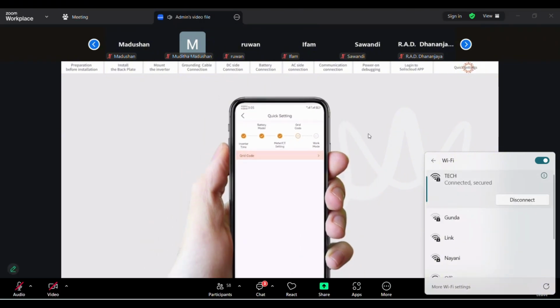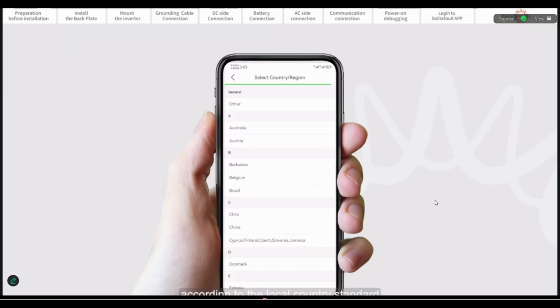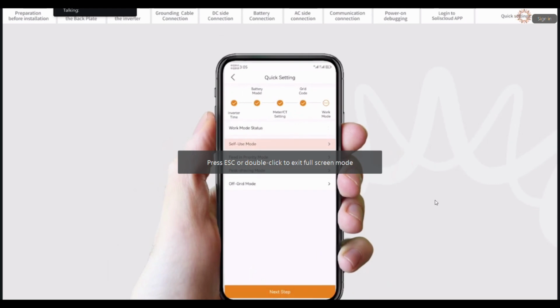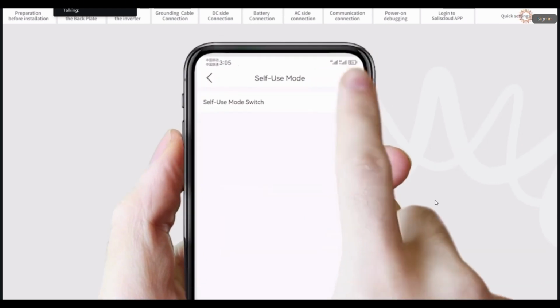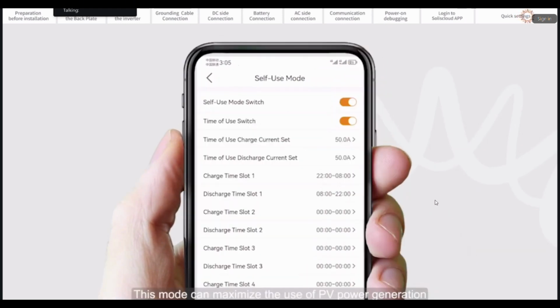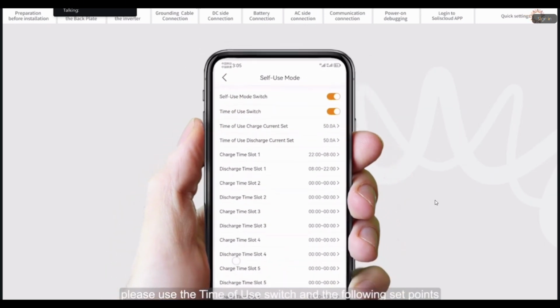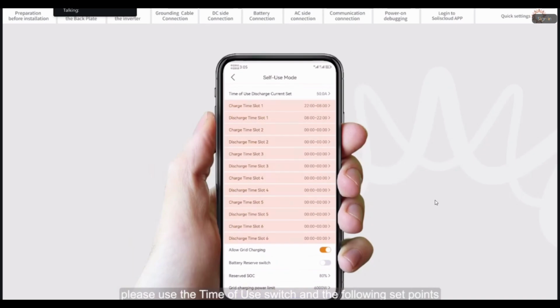Set the grid code. Please select the grid code. Set the work mode. We recommend setting to self-use mode. This mode can maximize the use of PV power generation for household electricity, or store it in the batteries and use it for household electricity. If needed, manually control the battery charging and discharging with respect to time. Please use the time of use switch and the following set points as required.